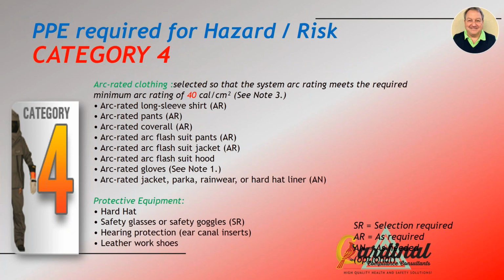Category 4 basically looks like you're going to the moon. You just put on a set of bibs, a coat, and it basically looks like a welder's hood, but it's an electrical Category 4 hood. It does have a welding type shield in it that's arc rated that would reduce the intensity of the arc flash so that you don't get eye damage. But it's a completely enclosed hood with an electrical hard hat inside of the hood so that you can withstand the pressures and the impact of that arc blast.